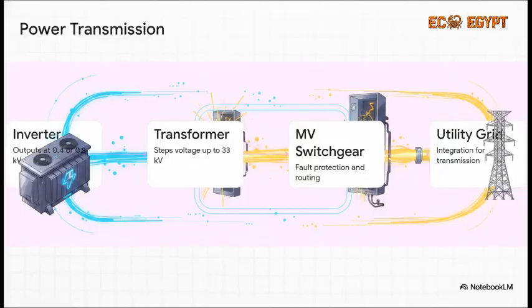Let's track the actual journey of an electron through the system. It starts at the inverter, which outputs around 0.4 or 0.8 kilovolts. Then, boom, it hits the power transformer, which steps that voltage way up to 33 kilovolts. From there, it routes through the MV switchgear for fault protection before finally making its way out to the utility grid. This sequence right here is exactly how you take multi-megawatt power and push it efficiently over long distances.